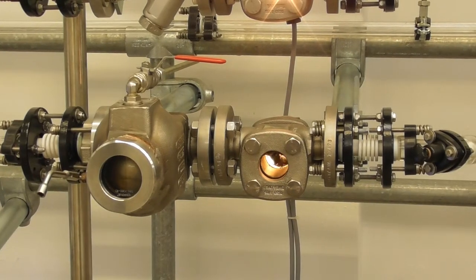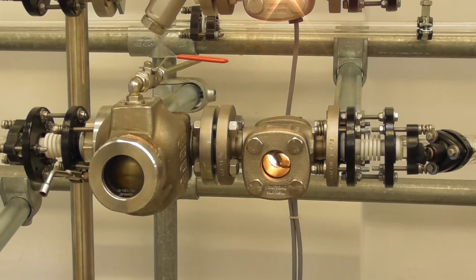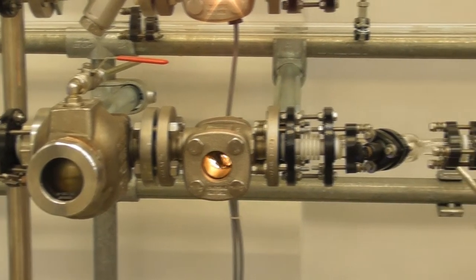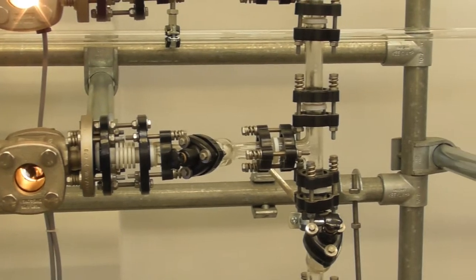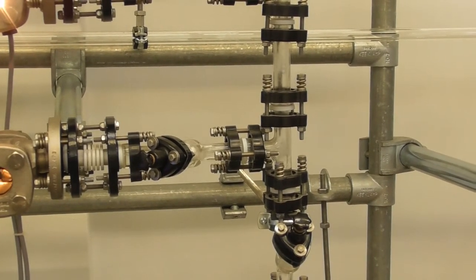Let's take a look at our ball float steam trap discharging the condensate coming from the heat exchanger. We can see through the sight glass that we got no banking up which is just fine, even though the steam trap is installed in the wrong position.